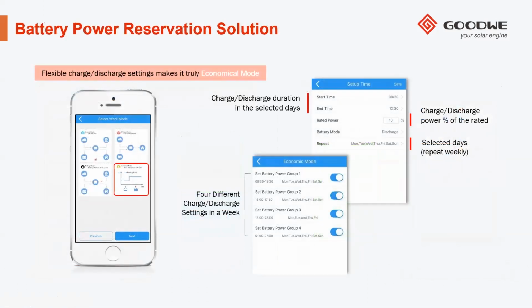Another option is the economical mode. Economical mode gives you a bit more flexibility. With the backup only mode, it charges at a UPS rate. So it charges at 10% of the rated charge current or charge power in the high voltage. What that does is slowly charge your batteries to ensure that if a large scale outage occurred and the grid comes back on, everyone's not charging the batteries at full steam at the same time.